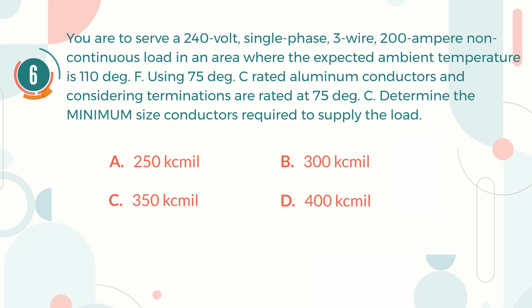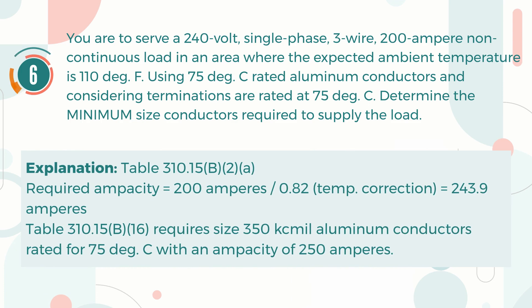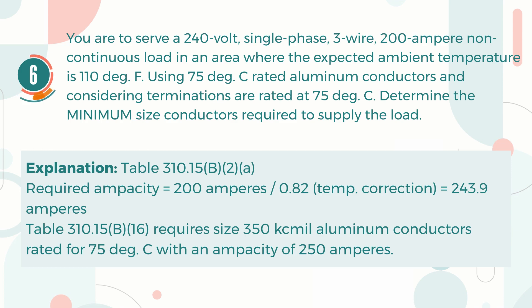The correct answer is C. 350,000 Circular Mil. Explanation: Table 310.15(B)(2)(a) indicates the temperature correction factor is 0.82. Therefore, the required ampacity equals 200 Amperes divided by 0.82, which equals 243.9 Amperes. Applying Table 310.15(B)(16), aluminum conductors 350 kcmil rated for 75 degrees Celsius have an ampacity of 250 Amperes.